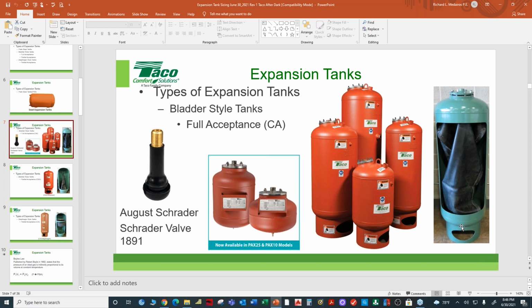Holy moly. Do you fill the tank bladder for correct GPM by a flow meter or PSI calculation? Wow, what was the question? Do you fill the tank bladder for correct GPM by a flow meter or PSI calculation? I'm not sure I understand that one. You never fill the expansion tank with fluid.